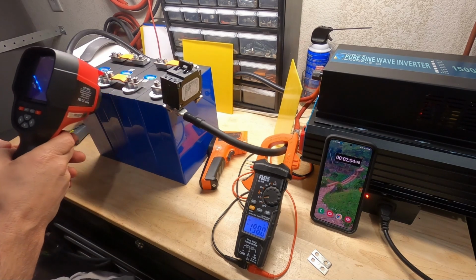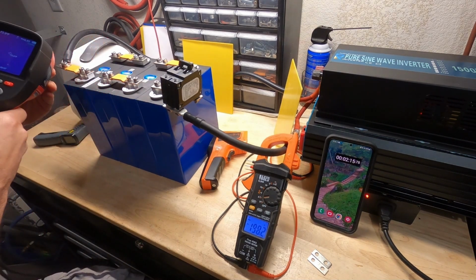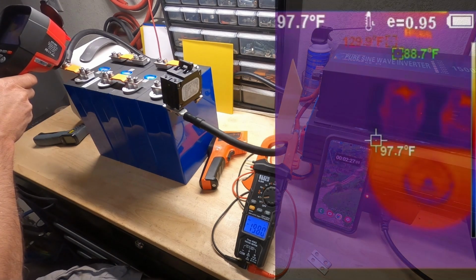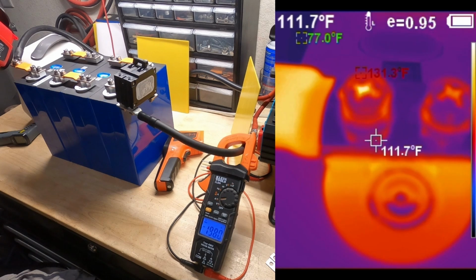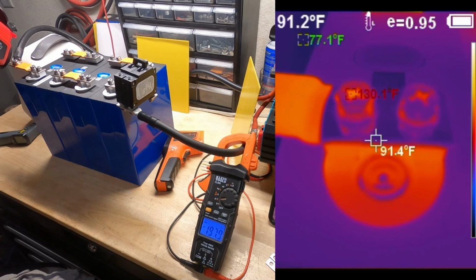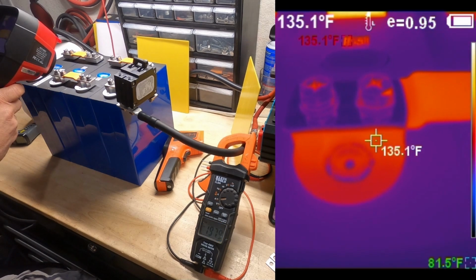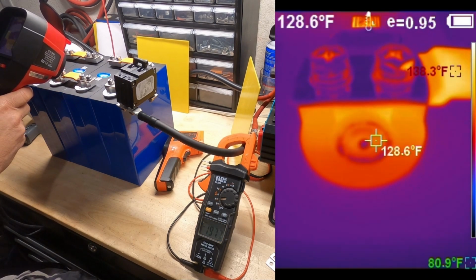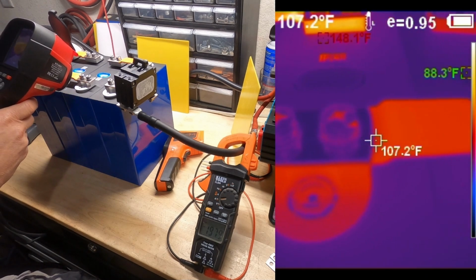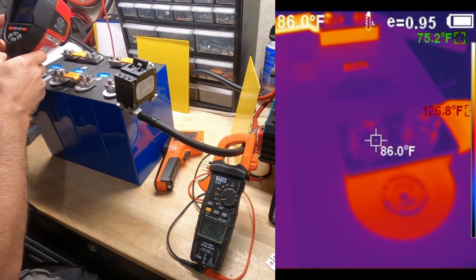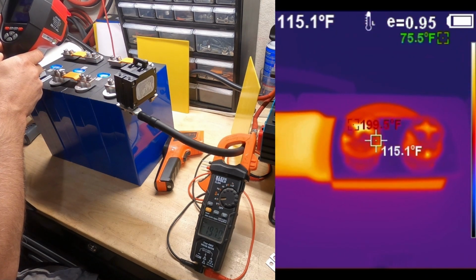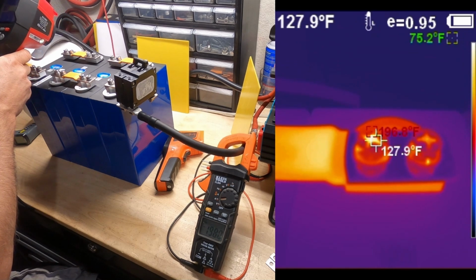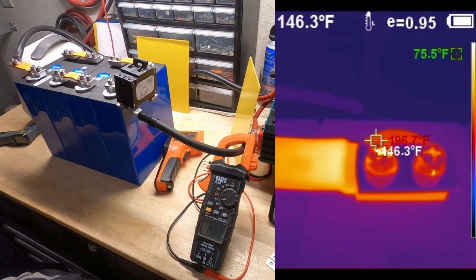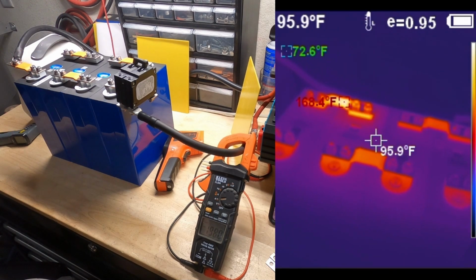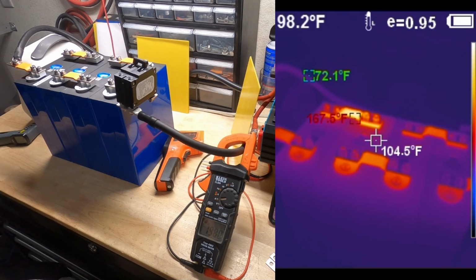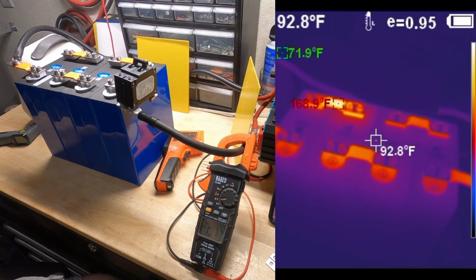Let's take our first heat reading. First, we'll check the bus bars. Looks like about a max temp. I can't read that red. It's 130, and our target is 100. 130 on the bus bar. 195 on that one. That's crazy on the max. That bus bar, if you look back, look at that. That particular bus bar. You can see over the whole pack, that one is definitely hotter.